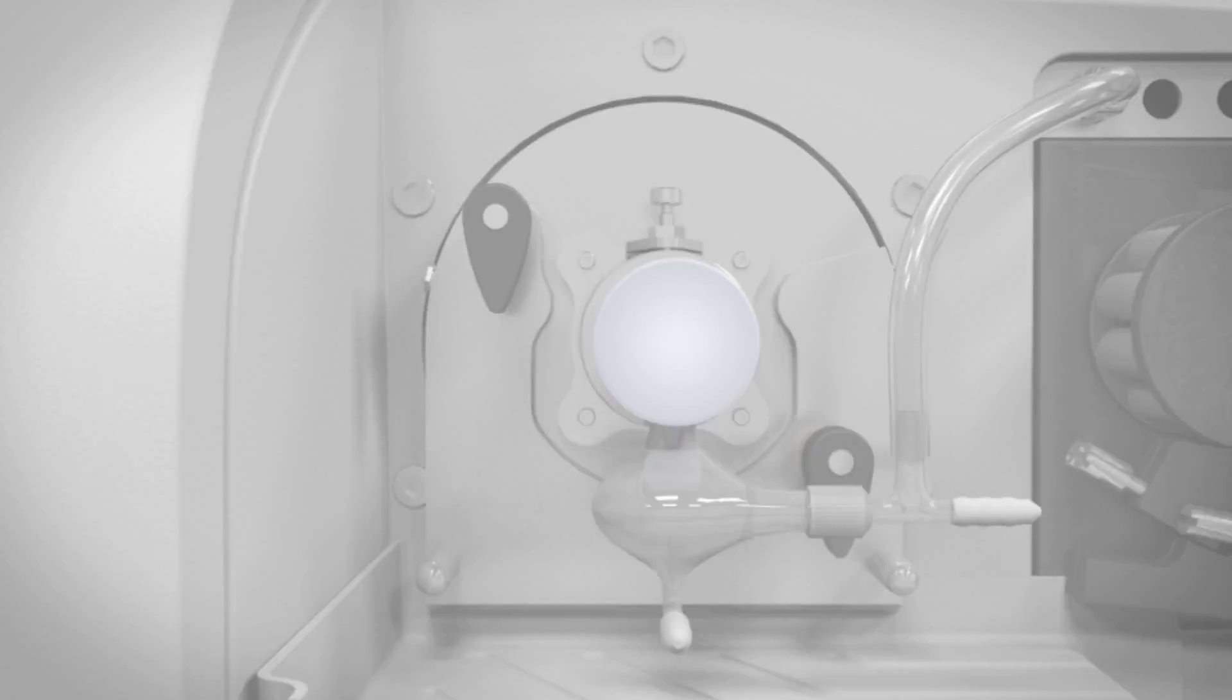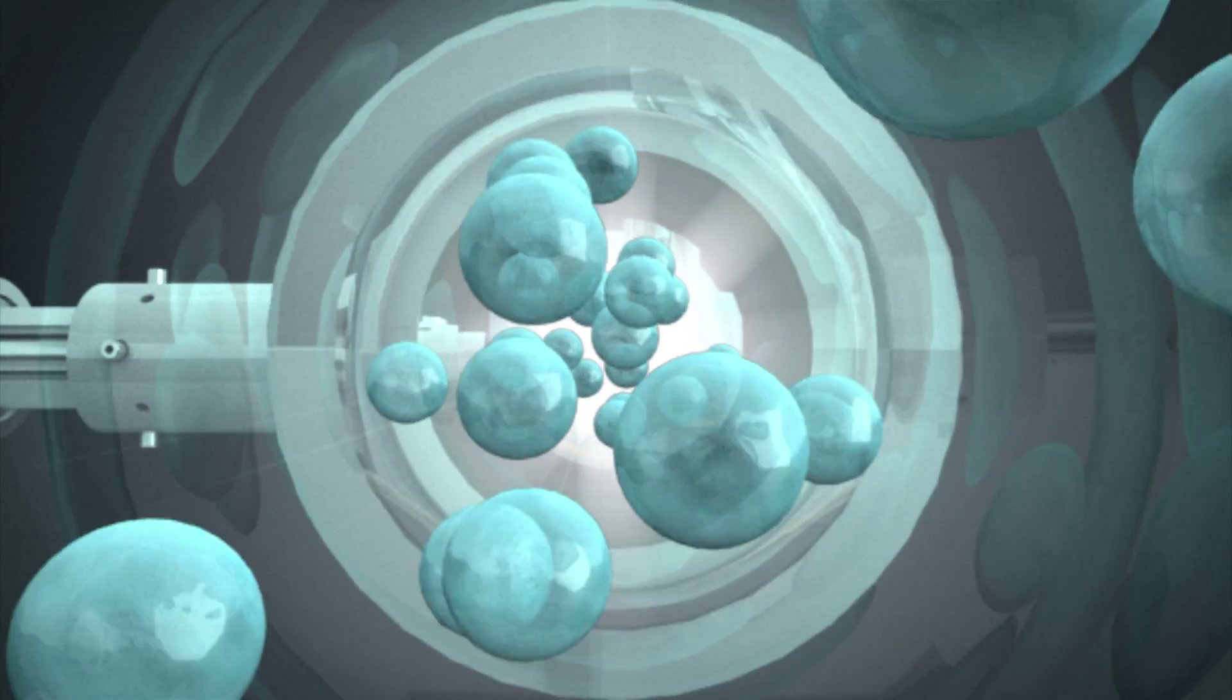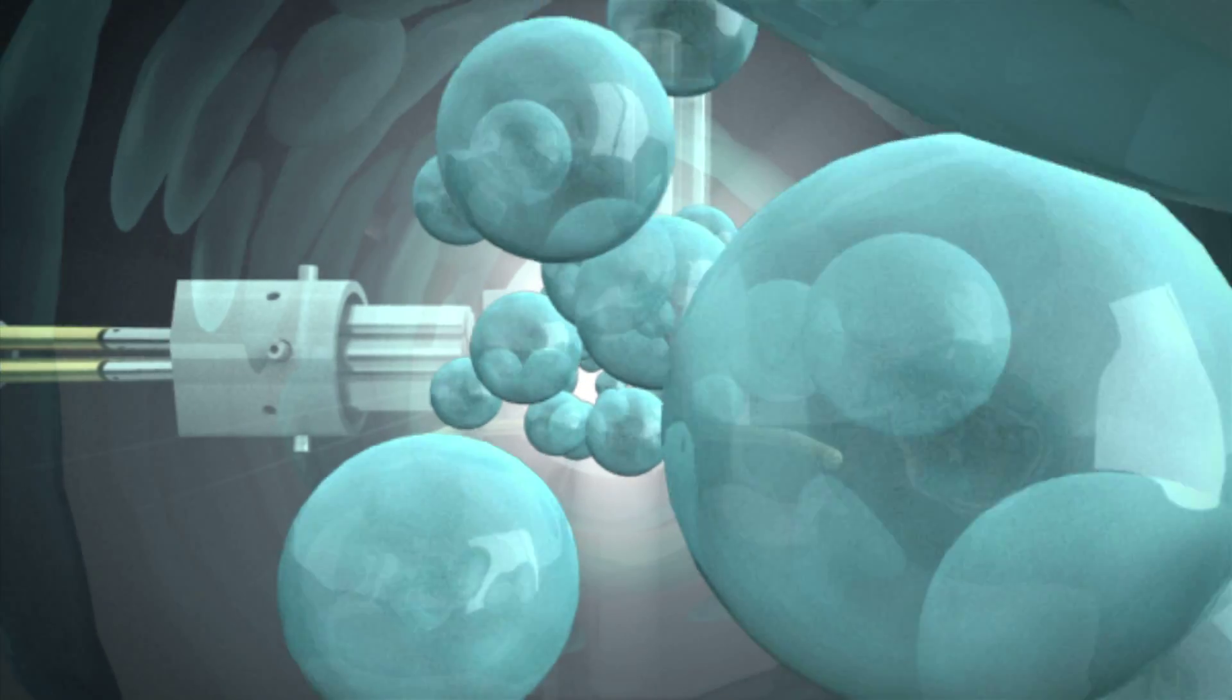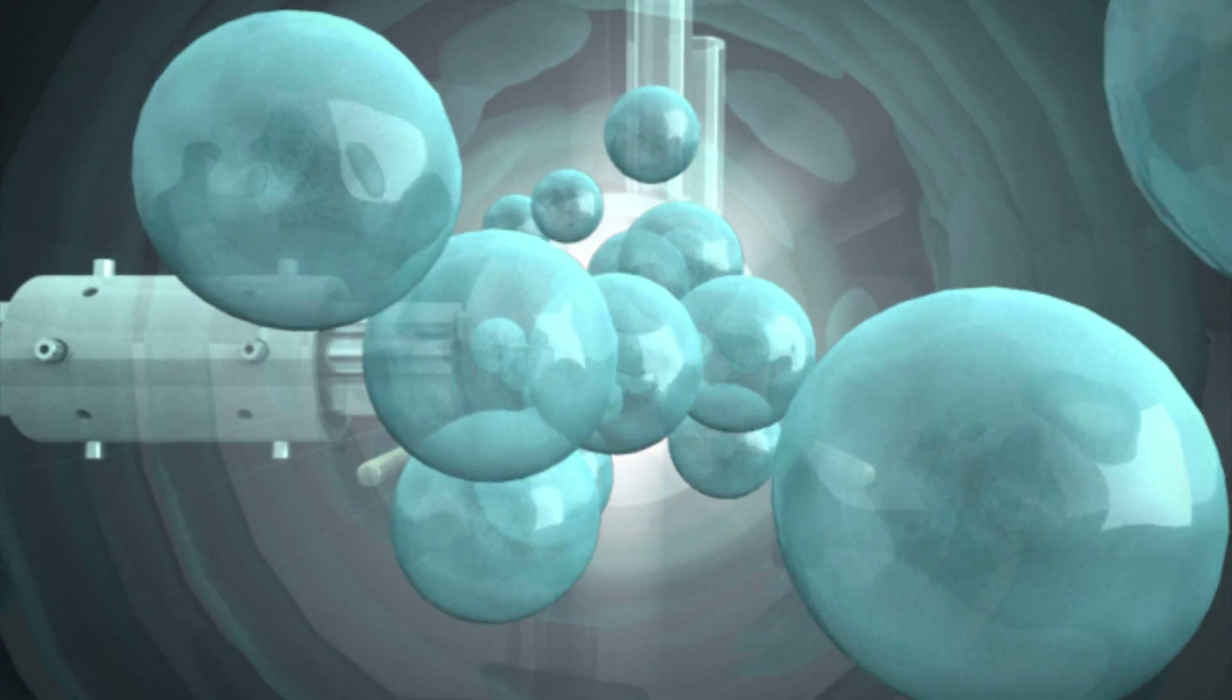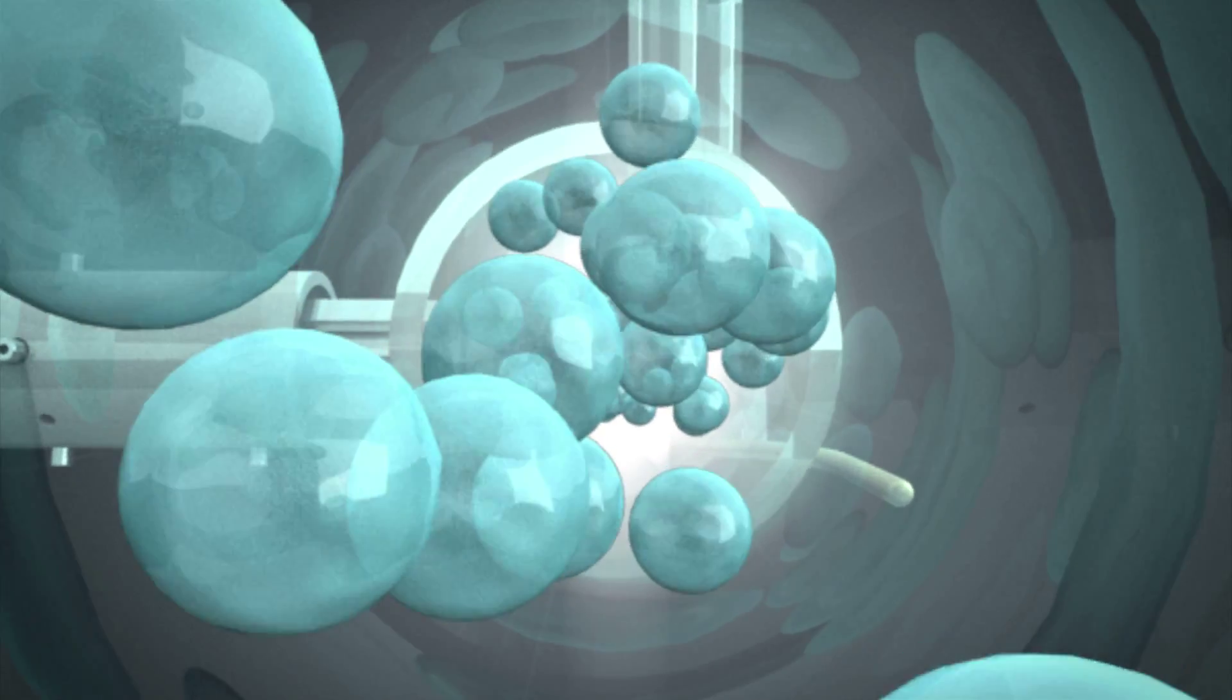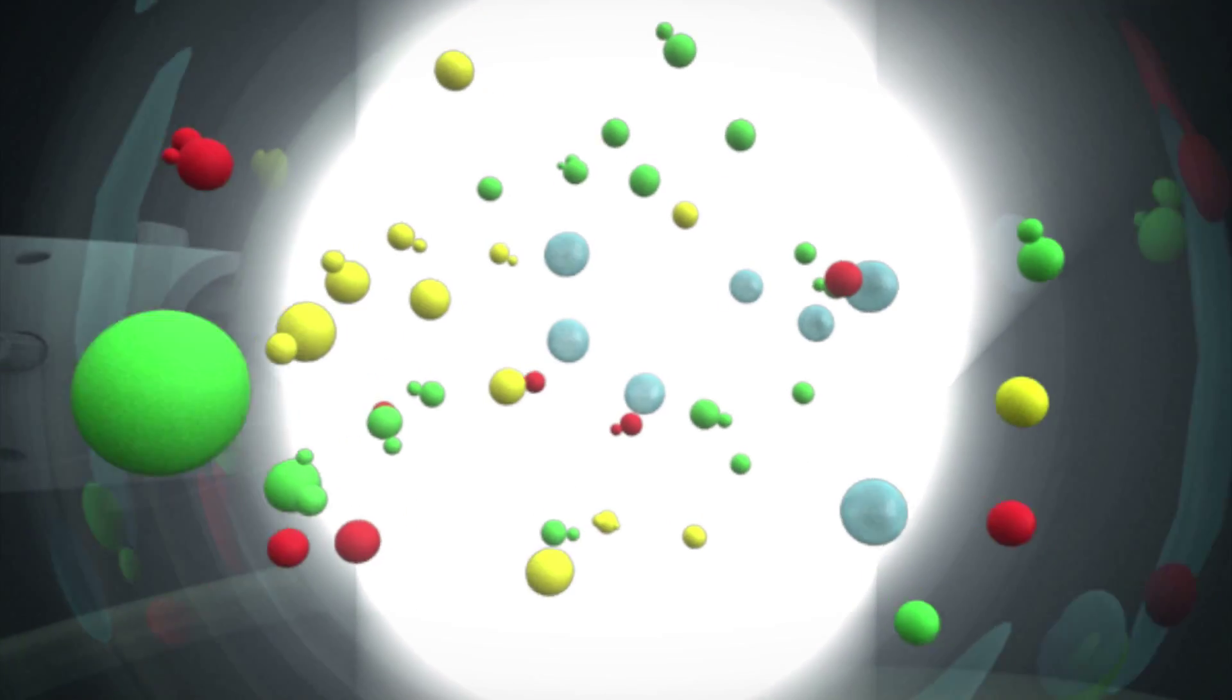Once your sample is introduced and has been converted into a fine aerosol in the spray chamber, it passes into the torch and through the argon plasma. Sustained by the most powerful and reliable RF generator in the industry and precisely aligned with a fully automated X-Y-Z adjustment capability, the plasma dries, atomizes and ionizes the sample.